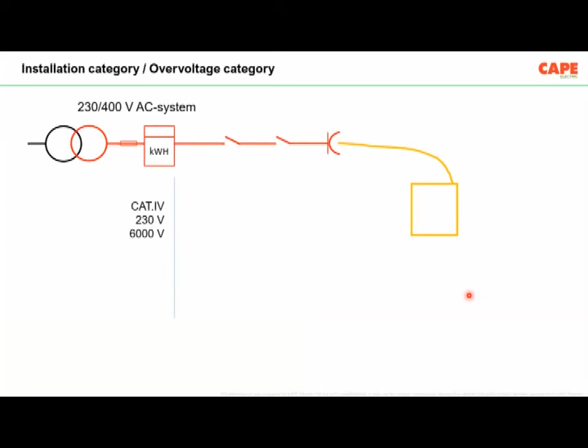The connected equipment must be of category 2, 2500 volt. These are the minimum voltage potential differences or voltage impulses the equipment are supposed to have. That means in your wiring, the minimum voltage impulse or the minimum category of the equipment is category 3. Connected equipment is category 2.